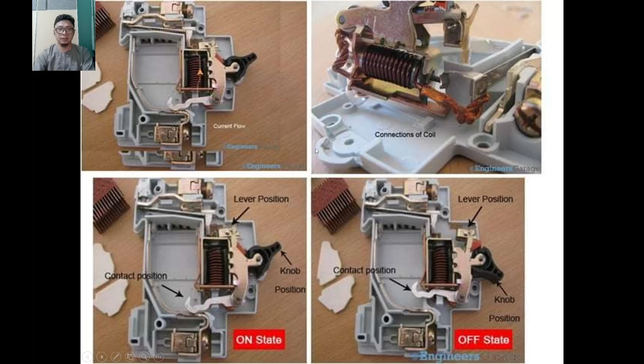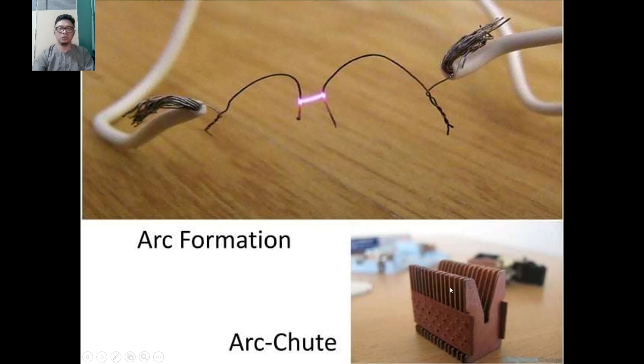And then I will explain to you about electrical arc. An electrical arc is formed if we have two cables with electricity inside. If we put them side by side, even if they do not touch, there will be an arc created. An arc is a jump of the current, and it is a very high temperature. So we need a part of the MCB to eliminate this arc. So we create the arc chute. This is to eliminate this arc.